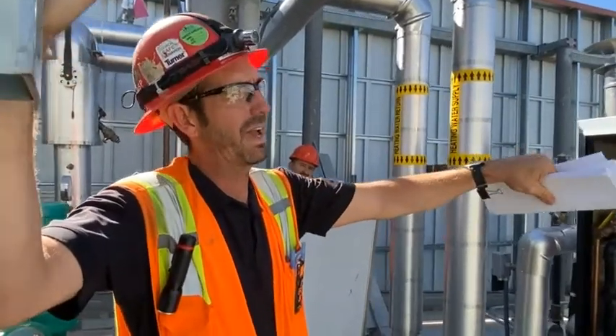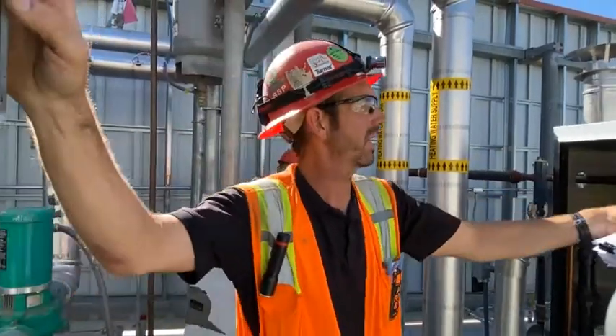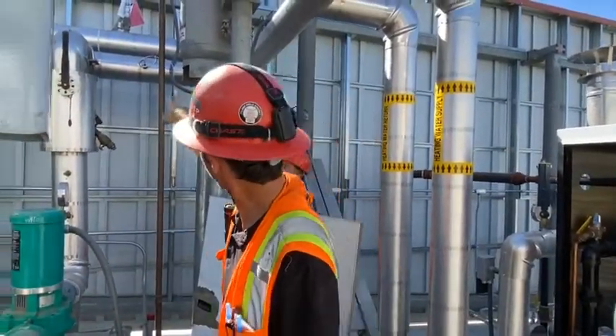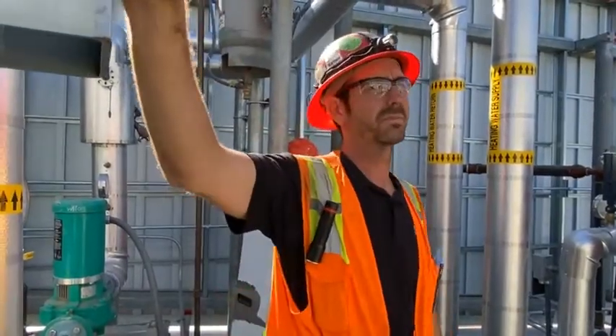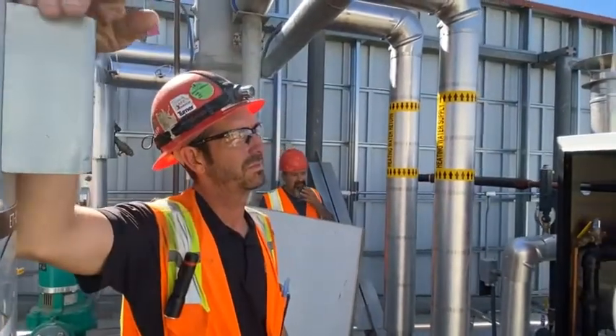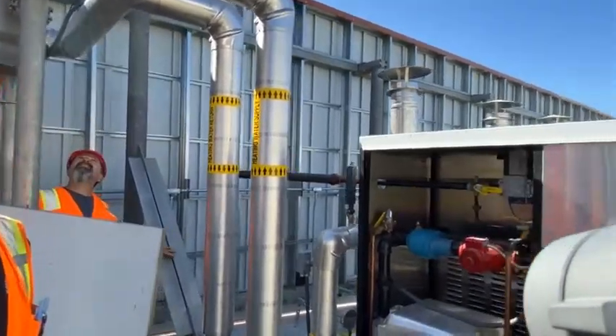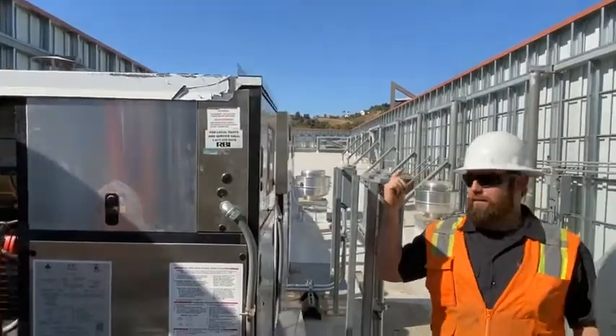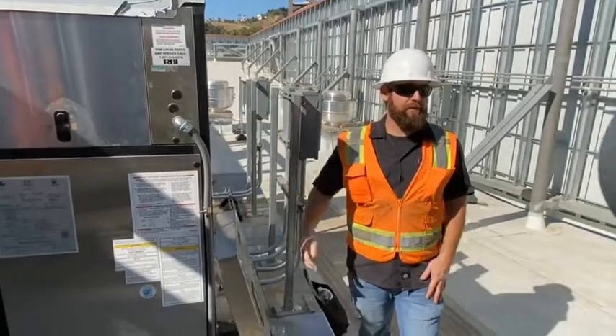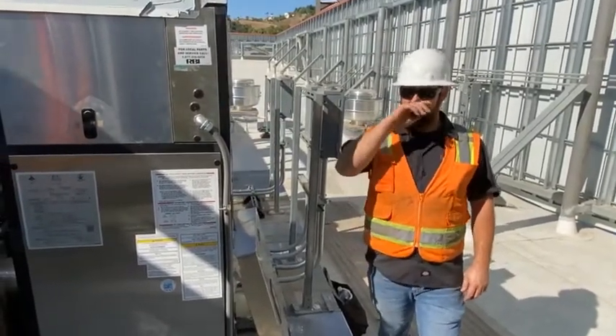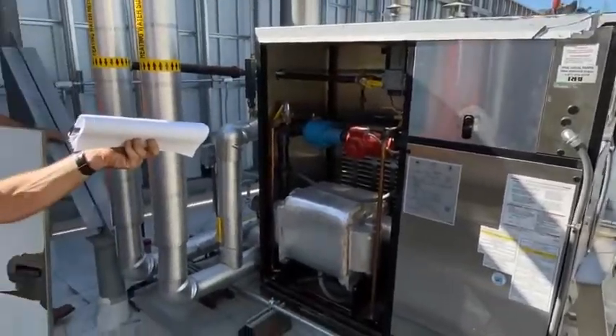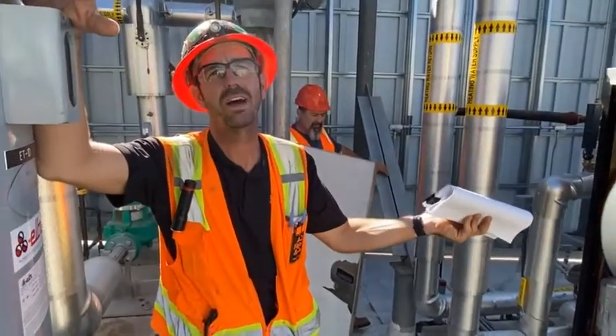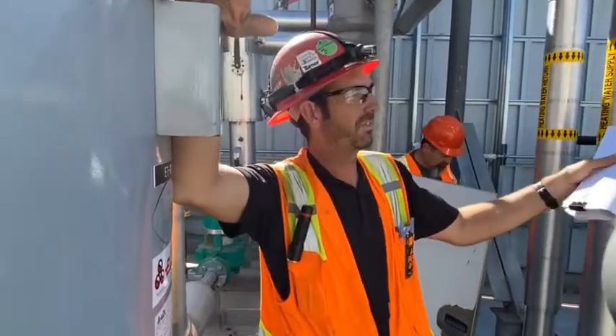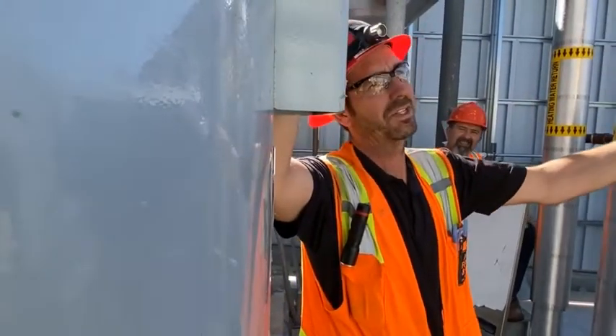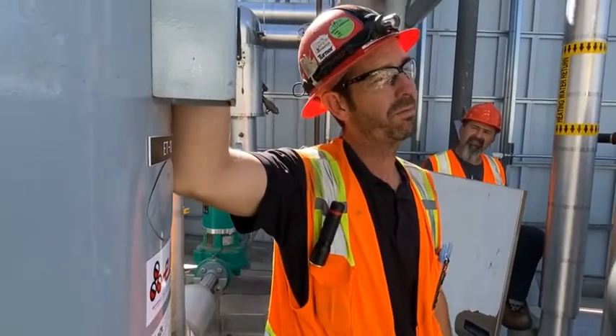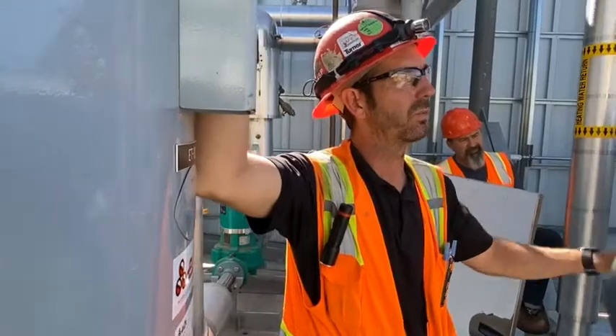If you have to do maintenance, the master is also getting its temperature from that sensor right up there. Header sensor. The header sensor. It's a good point. If this has to be shut down for any reason, power turned off, you have to put the other two into local mode. They're not going to be receiving a signal from the master if the power's off. So if you come up here on a call that they don't have hot water, then obviously you're going to need to figure out if this is off. Then we'll need to open up those other two panels and switch both of them into local mode, and then they'll just internally work off of their own temperature.